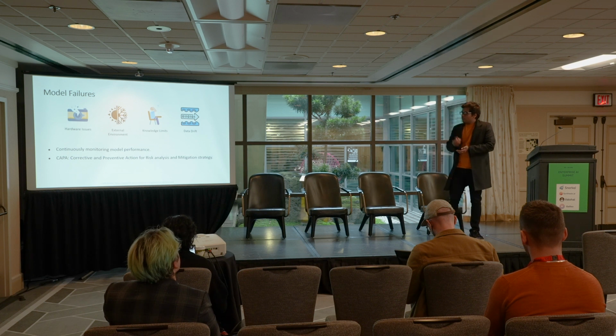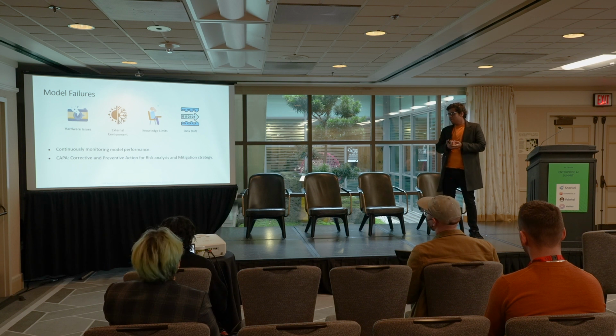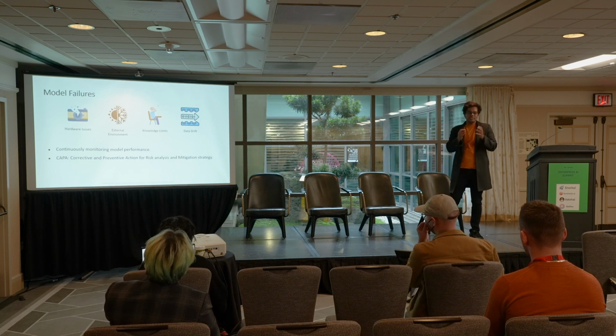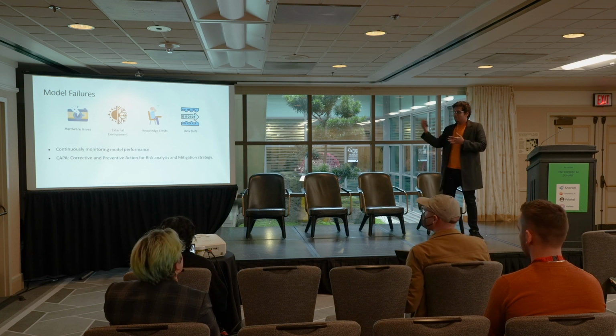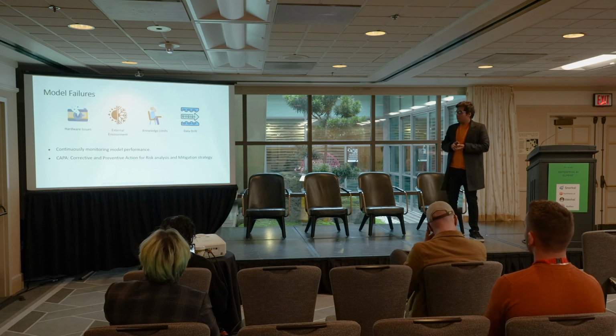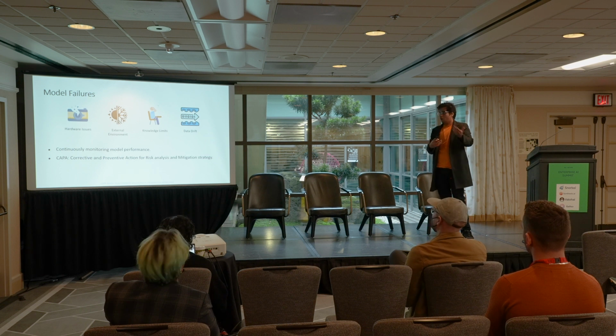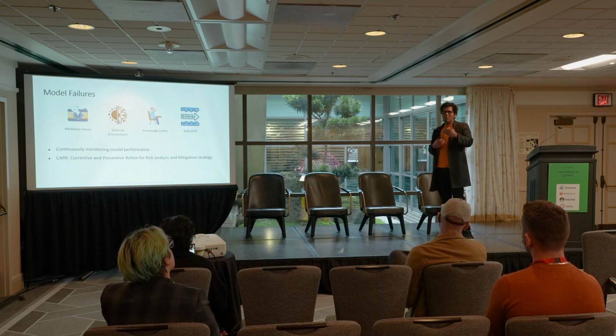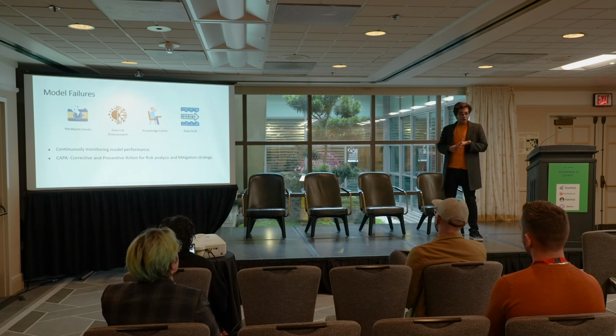And the FDA has, this is an old terminology, we call it CAPA, which is corrective and preventive action. If something goes wrong in the field, people will raise flags, and you have to go and address that concern based on the severity of how big a problem that is, and whether you have to recall the product. Or basically you go about debugging what went wrong in that situation, whether it was a model issue, whether it was a hardware issue, whether we ran into certain knowledge limits.